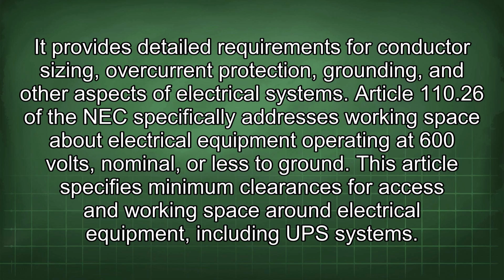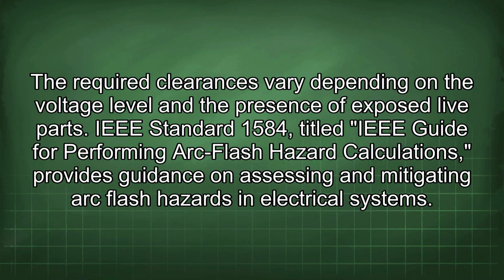Article 110.26 of the NEC specifically addresses working space about electrical equipment operating at 600 volts, nominal, or less to ground. This article specifies minimum clearances for access and working space around electrical equipment, including UPS systems. The required clearances vary depending on the voltage level and the presence of exposed live parts. IEEE Standard 1584, titled IEEE Guide for Performing Arc Flash Hazard Calculations, provides guidance on assessing and mitigating arc flash hazards in electrical systems.